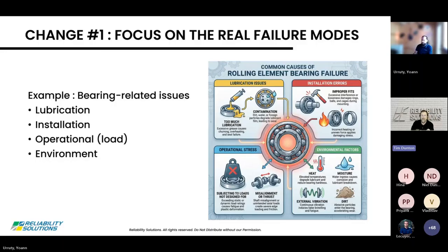We talk about bearing failures, and we categorize them to try to simplify things a little bit, divide and conquer: installation, lubrication, operational, environment. And again, the number one issue with a bullet, by far and away the biggest source of bearing failure that we see for installation is fits. We do a terrible job of fitting bearings to shafts and fitting the housing, right? We don't mic the shafts. We don't do everything we're supposed to do there. It's terrible.